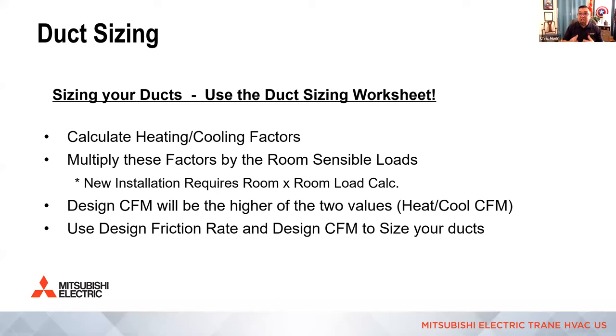All right. So that's why in order to do a new duct system, we actually have to have a room by room load calc, because we need the sensible loads for each room to know how much volume of air goes to each room. That's how we size the runs. The design CFM is going to be the higher of the two values. Just because a heat pump runs typically at the same volume of air does not always mean we design around cooling or heating.